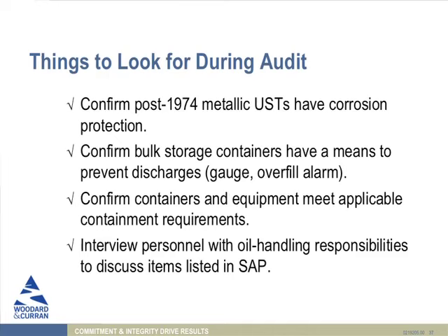I was inspecting a facility last month, reviewing the monthly inspection records of the tanks, and somebody had written across the form, "I've not had training, I can't do this inspection." And somebody just filed that away with all the other inspections. So, watch for things like that and make sure that people who have responsibilities know what they are.